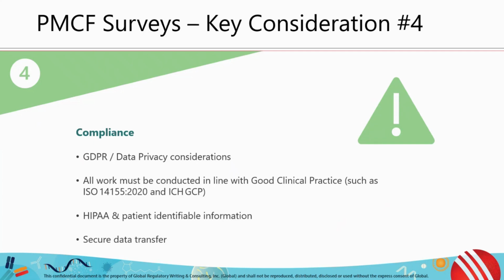Finally, it's important to think about compliance. This is European regulation. You're collecting European data. You're collecting safety data. You may be collecting contact information. So think about GDPR and data privacy considerations. Ensure your work is conducted in line with GCP, looking at ISO 14155. If you're collecting patient identifiable information, you need to consider how you can do that. Are there any approvals needed, for example? And if you are sharing data such as patient identifiable information or personal data, you need to make sure it's being transferred securely as well.